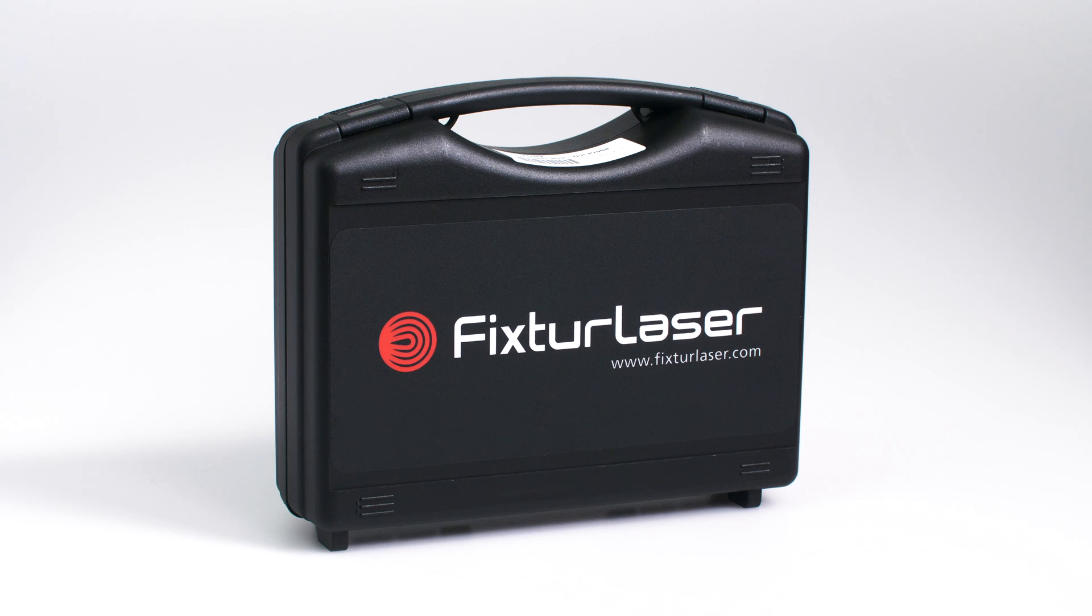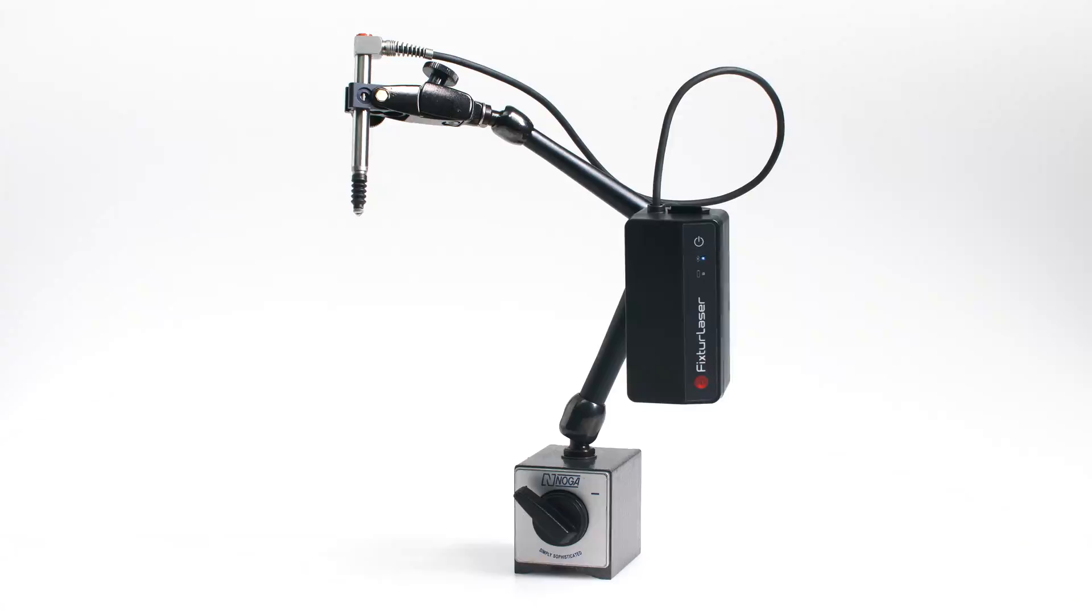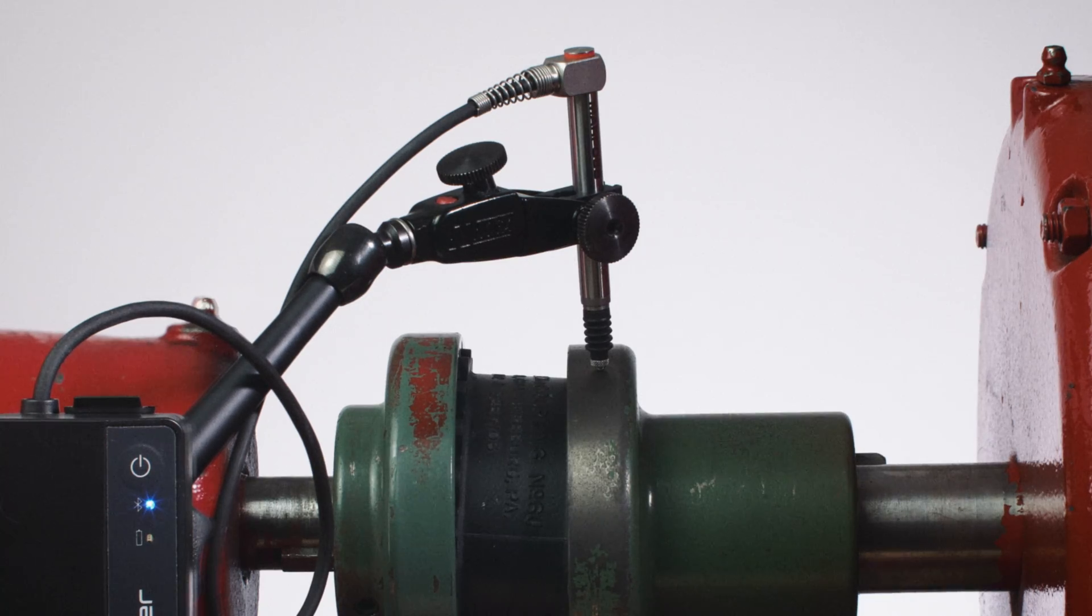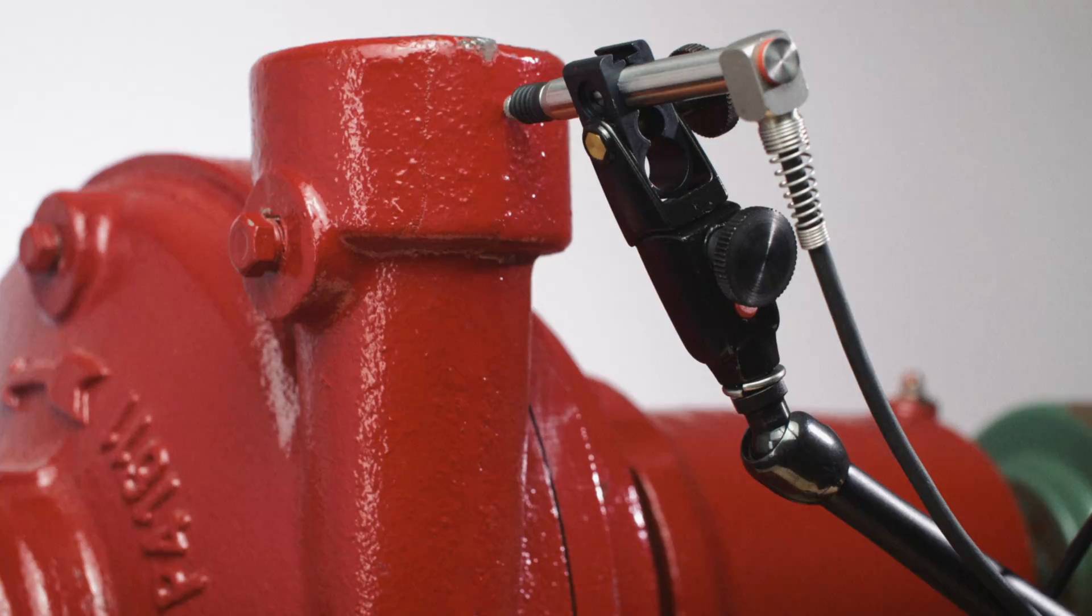The FixturLaser Runout Probe comes in its own carrying case which includes the sensor, Bluetooth unit, and an articulated arm attached to a magnetic base. The arm is designed so the user can position the sensor as needed to take measurements from the coupling, the shaft, and the pipe flange.